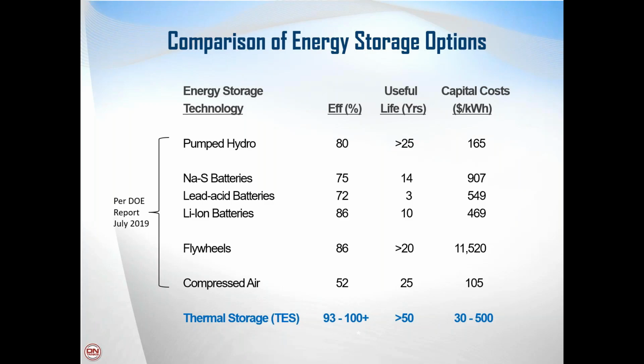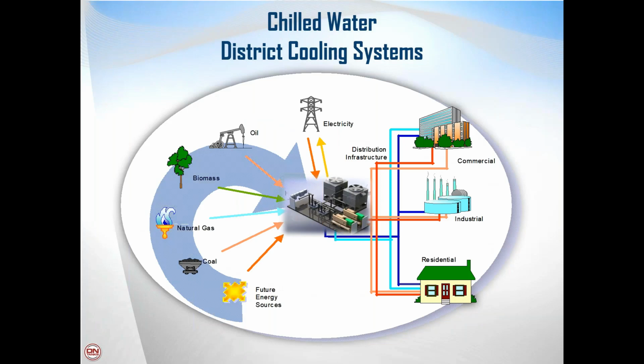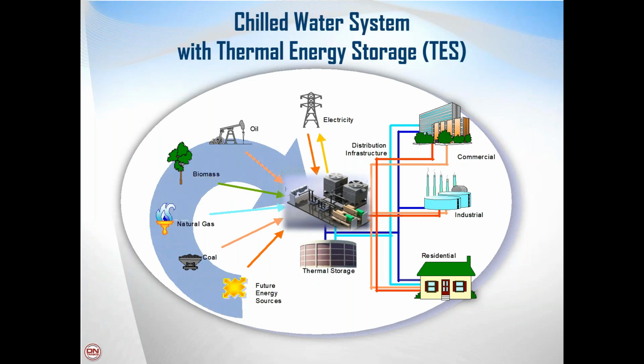How can I utilize thermal energy storage in my systems? The best way to do it is if there is a chilled water district cooling system associated with a facility or a campus. And that is in the center of the presentation. You're looking at a chilled water cooling plant, and that is providing chilled water with very large horsepower chillers. It pumps that chilled water out to the building or the campus. That cold water then is used for cooling or processes, and it returns back to that central plant for recooling again. So it's a closed loop chilled water system that could possibly use a thermal storage tank.